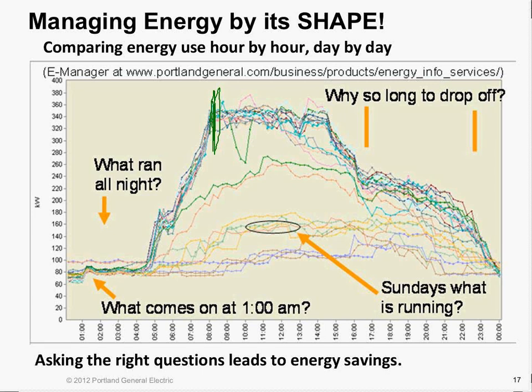And then somewhere around 3 o'clock or so, people start leaving the building, and you have this slow decline back down to midnight. What you have is Monday through Friday up at the top. You have Sundays here, and you have Saturdays here. The 4 or 5 Saturdays, the 4 or 5 Sundays, and then all the Mondays through Fridays. So suddenly the chart can start making some sense with a simple explanation.